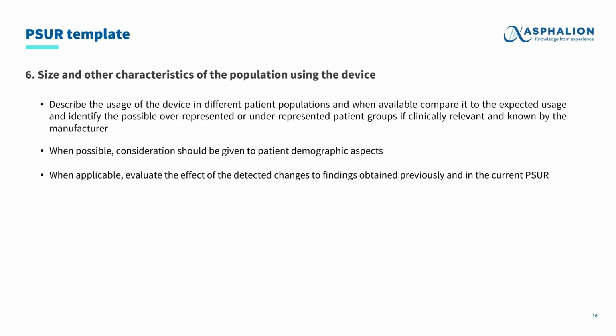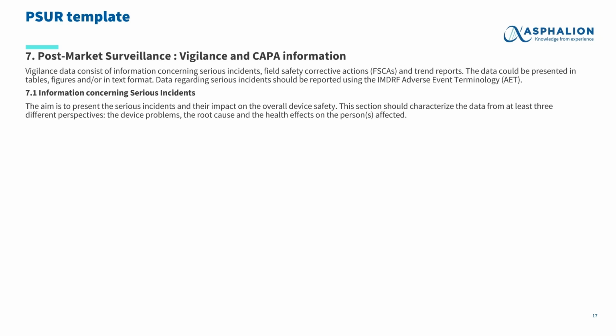And also finally, when applicable, the manufacturer should evaluate the effect of any change detected during the reporting period in comparison with previous PSURs, and a justification of this change should be stated in this section. And after estimating the number of patients exposed to the device, it's time to include all data collected from the post-market surveillance activities. First of all, vigilance data will be included, which consists of information regarding serious incidents, field safety corrective actions, trend reporting, and CAPAs.